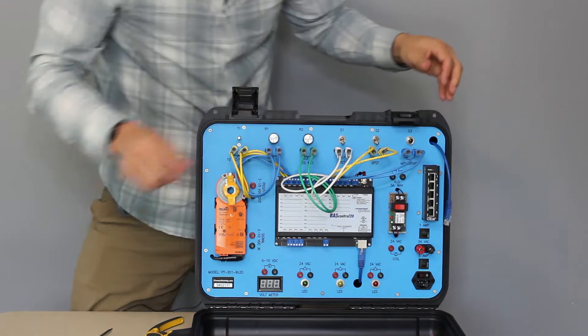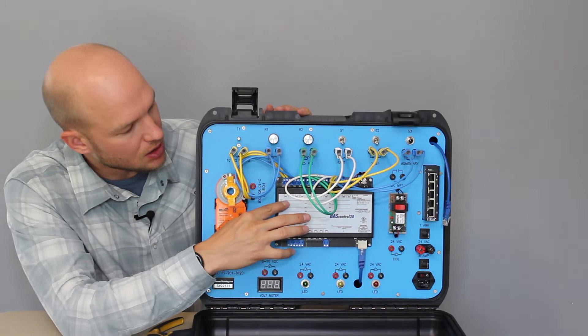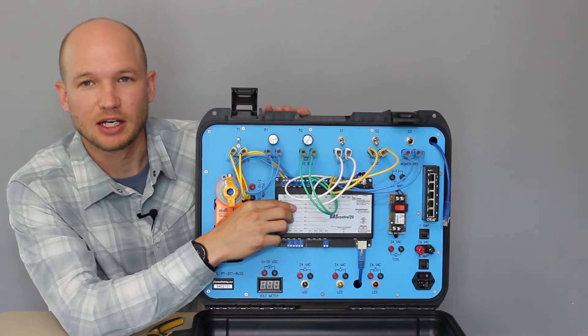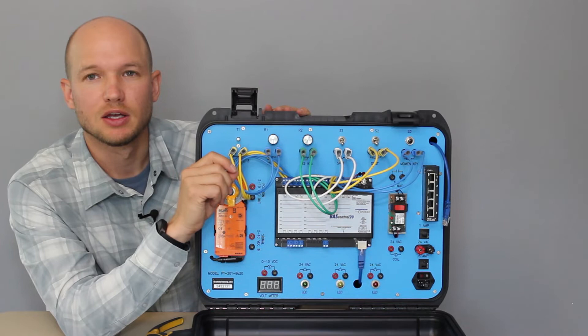One thing that's nice about the controller is that all the inputs and outputs are short circuit protected and over voltage up to 24 volts protected. So let's say you're wiring up the connector and you have one strand that crosses over to the other side. So you're short circuiting A to C, it's not going to burn out or ruin the controller.